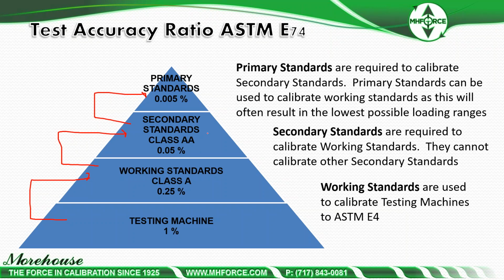Now, after 120,000 pounds, we use a 1,000,000 pound standard that was calibrated by NIST. We can supply only Class A, because we have a secondary, we can only supply Class A for any measurement over 120,000 pounds. We also have 3 1 million pound load cells that go to NIST, so we can apply Class A calibrations up to 10 meganewtons or 2.25 million pounds.